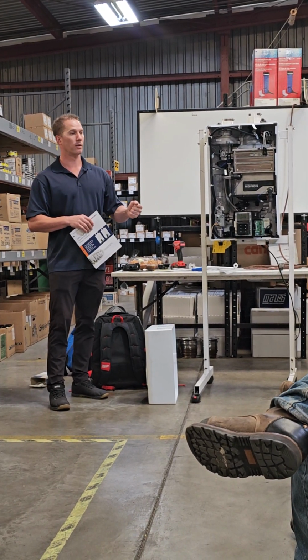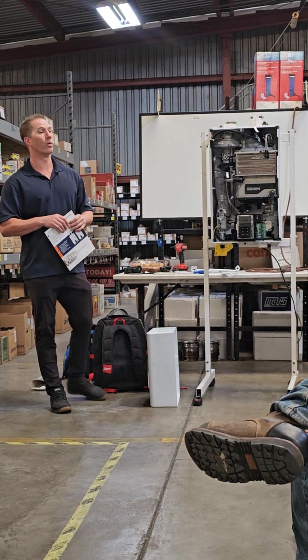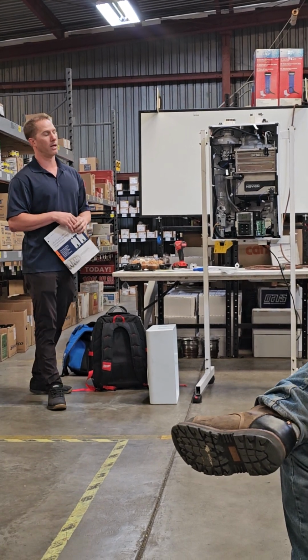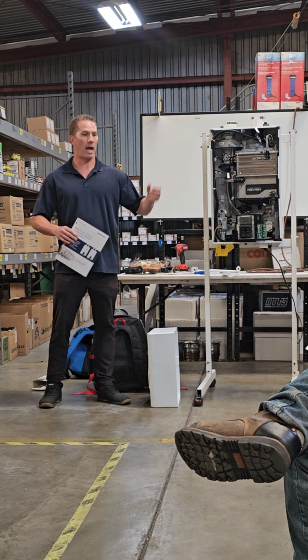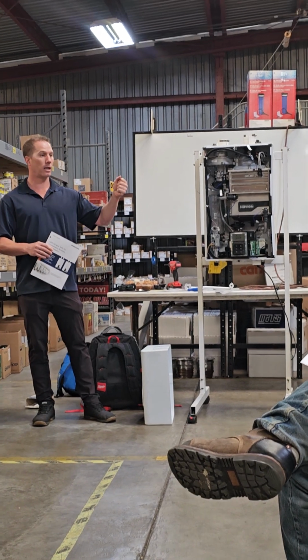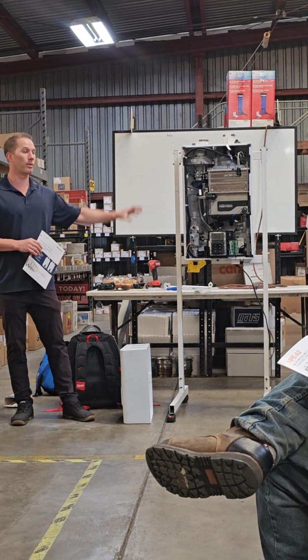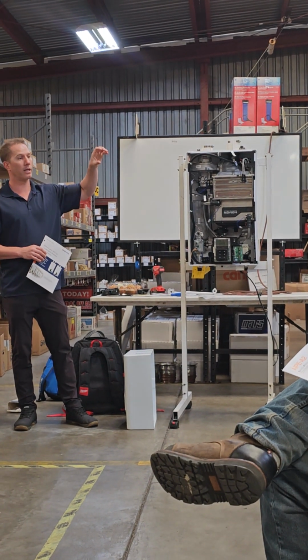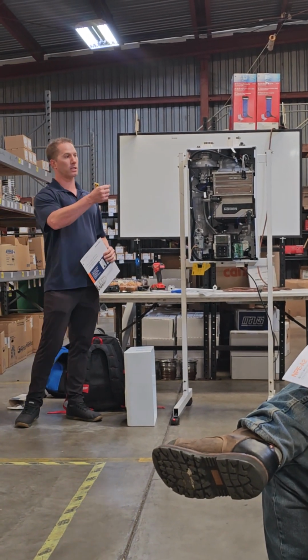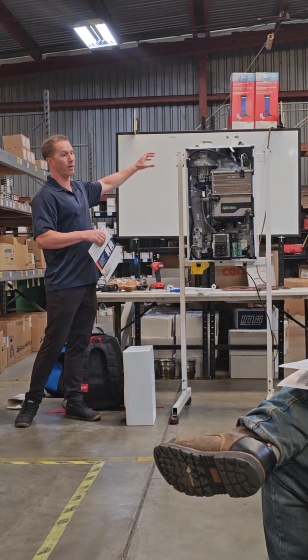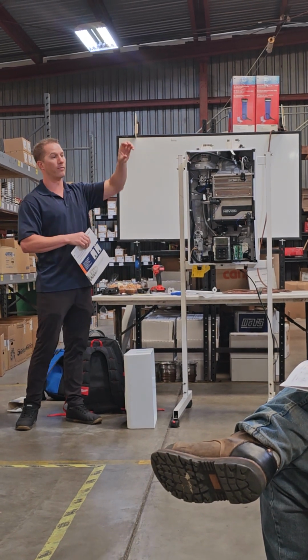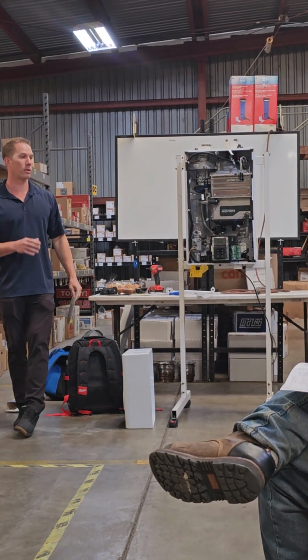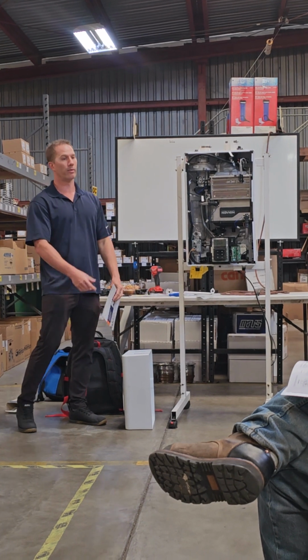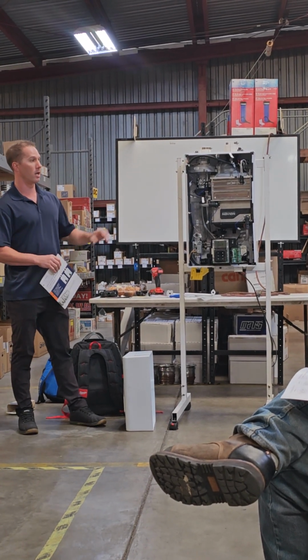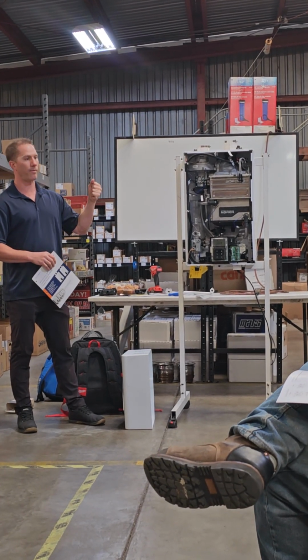So if, from the meter? No, from the branch line? From wherever the branch is, yeah. If the half-inch line is coming off of a 1-inch line, then that's fine, because there's plenty of volume and gas in that 1-inch line. But if the half-inch line is coming off 3/4 and there's a long run of 3/4, there's probably not enough volume and gas in both of them. In the main one, but yeah, 24 feet of half-inch line, as long as there's enough gas wherever the half-inch line is plugged into.